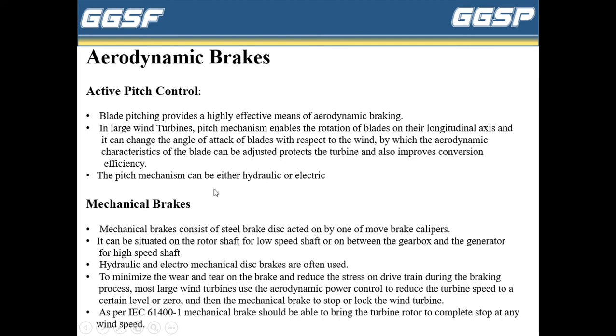The pitch mechanism can be either hydraulic or electric. Mechanical brakes. Mechanical brakes consist of a steel brake disc acted on by one or more brake calipers. It can be situated on the rotor shaft for the low speed shaft, or between the gearbox and the generator for the high speed. Hydraulic and electromechanical disc brakes are often used.